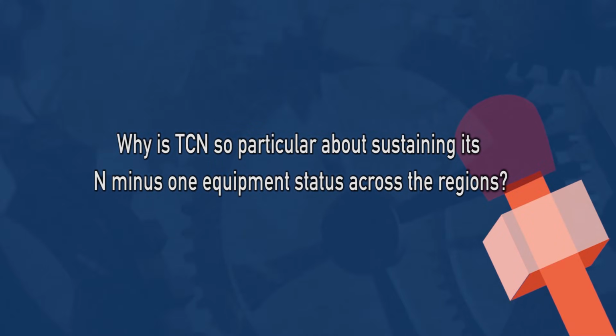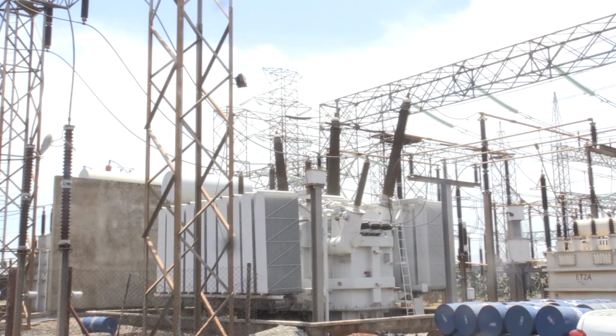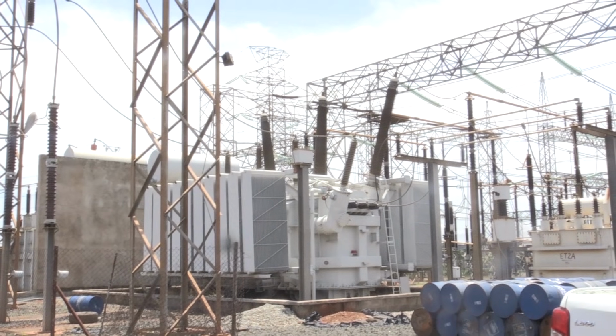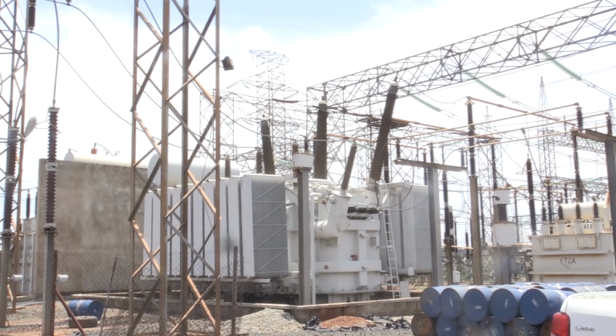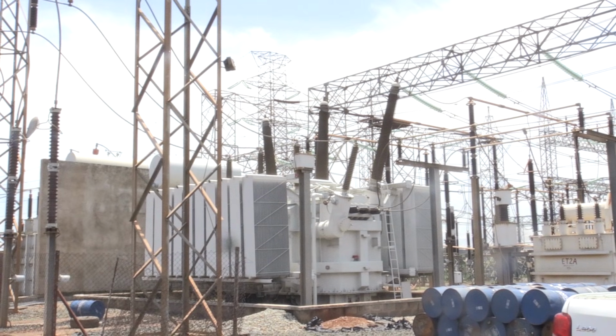Why is TCN so particular about sustaining its N-1 equipment status across the regions? This is the redundancy term. When we have 2 transformers, when one goes off, the other will come in so that there will be stability. But when you have only one, if it trips and faults, it means the customers will be out, there will be no supply for them. So that is the system we are using to ensure continuous supply and stability in the system.